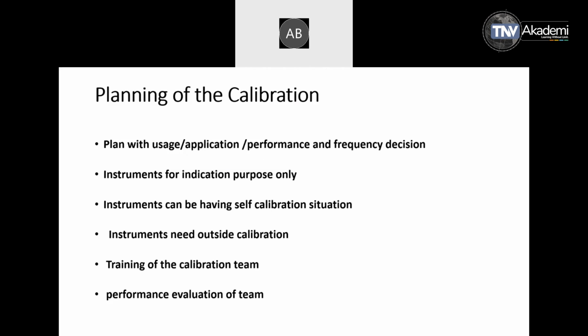Planning is one of the most important activities in calibration also. Sometimes there was a feeling earlier, when we started doing certification in the late 1980s and the beginning of the 1990s, that everything has to be calibrated. So there was a lot of debate going on among the auditing teams, inspection teams, calibration houses, even accreditation boards. A thought came very clearly that all this depends upon how the instrument is used, what the application is, what the performance of that instrument is, what the performance of the item being measured is going to be, and what the frequency of decision making is.